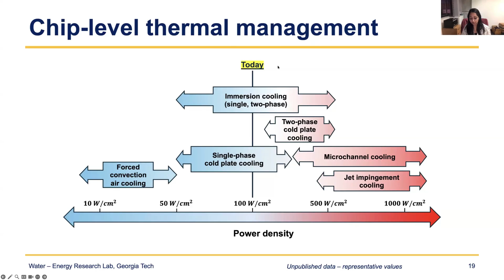And then to work with the transient peaks that occur: if you have a large spike in power, a thermal system cannot respond quickly, it takes longer to respond. So you need some kind of buffer to take the thermal load and dissipate it over a longer time scale. Phase change materials are really suitable for this, because by definition, when phase change is happening, you maintain the temperature. It keeps the temperature at the safe operating limit and acts as a thermal buffer, undergoing melting. Then that melted phase change material has to re-solidify by rejecting the heat, but you're essentially just increasing the time scale.